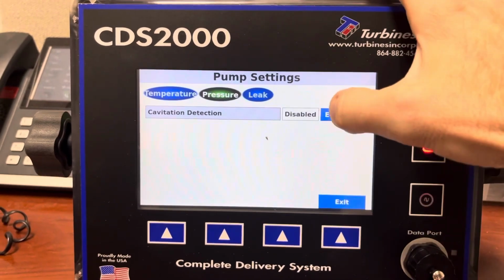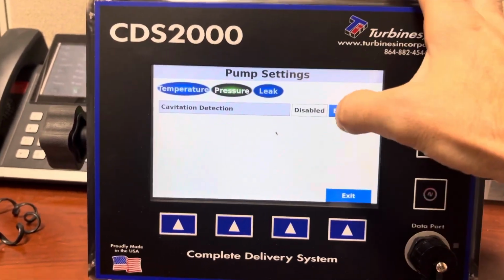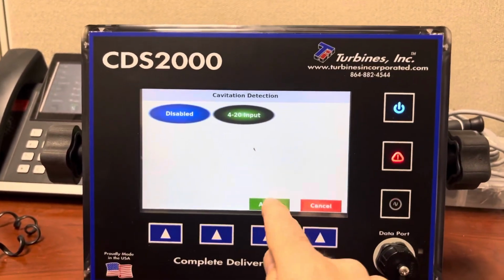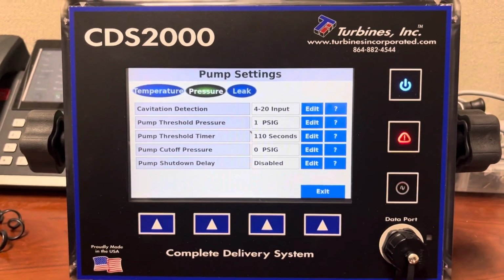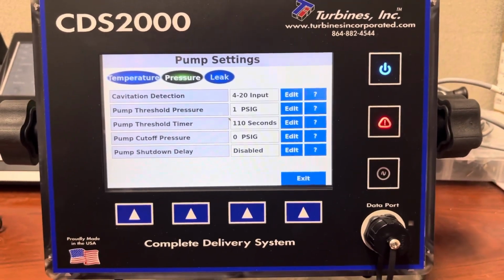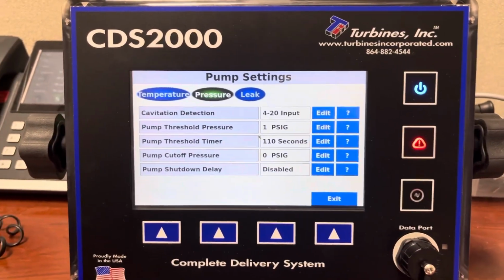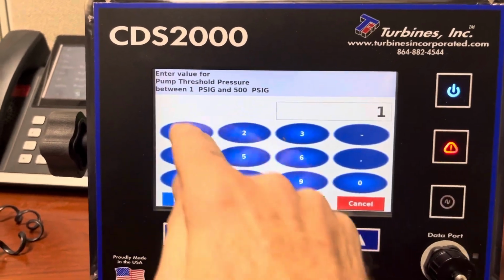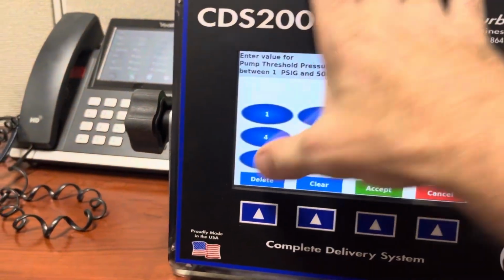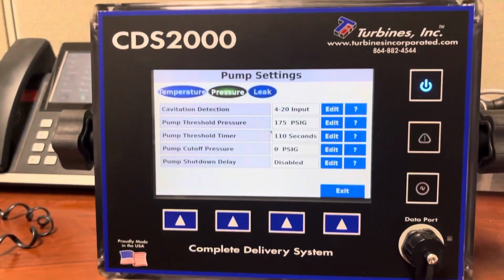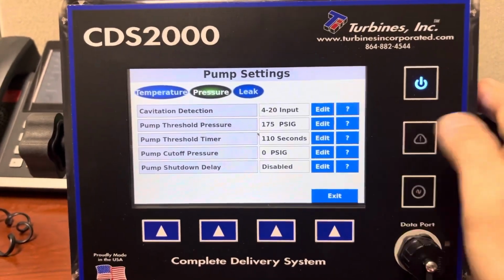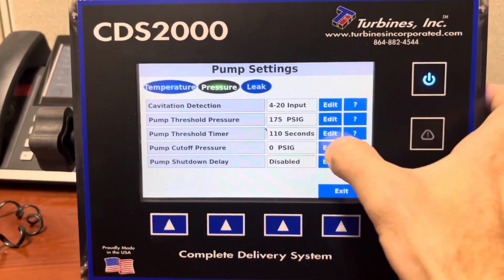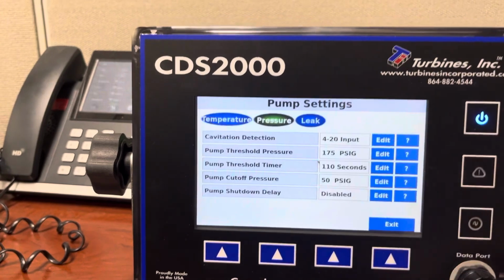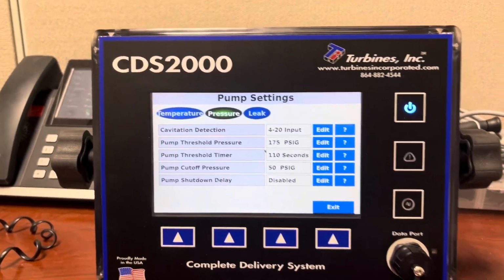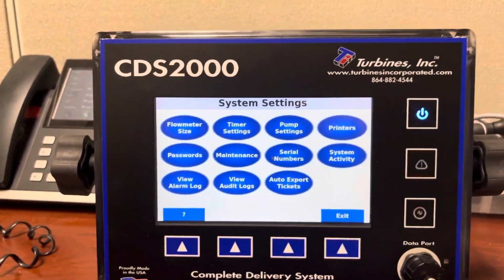I have this set for disabled, and it will come disabled from the factory. All you do is change that to 4 to 20 input. And again, all of the features that are in the CDS1000 are there for you in the CDS2000. Your threshold pressure should be set to maybe 175. If you're in nitrogen service, your threshold timer is the time it takes to achieve prime, and then your cutoff pressure is typically set for 50. Shutdown, delay, disabled. Other than that, there's not a whole lot more else to it.